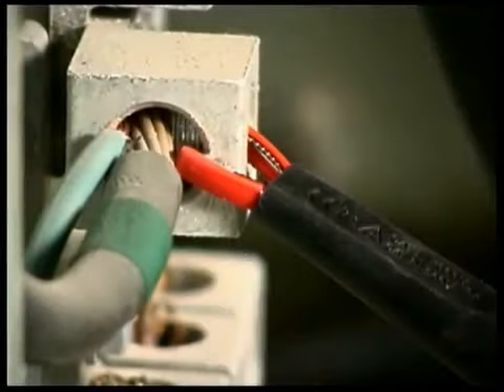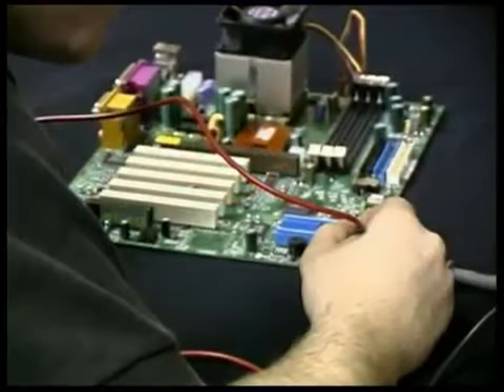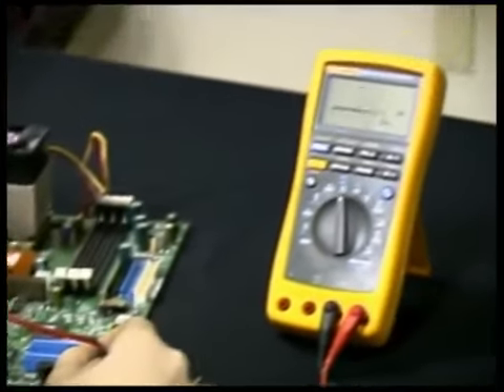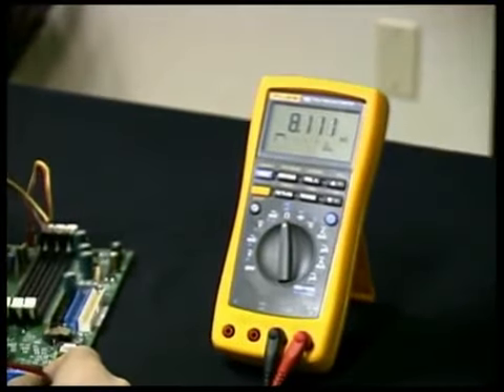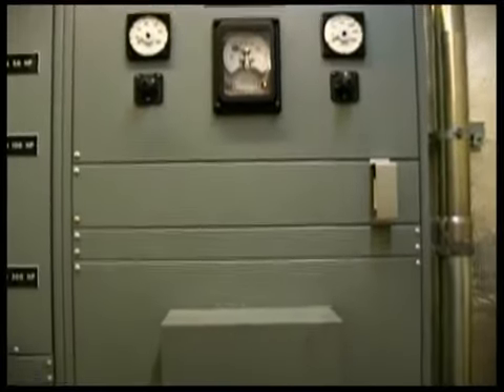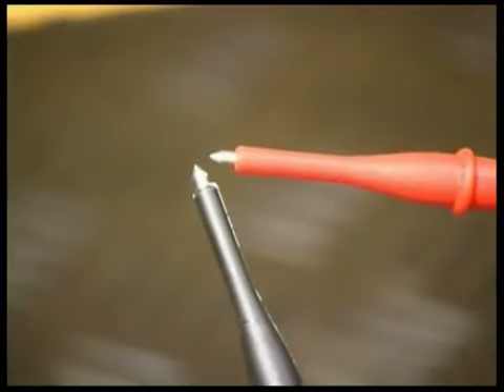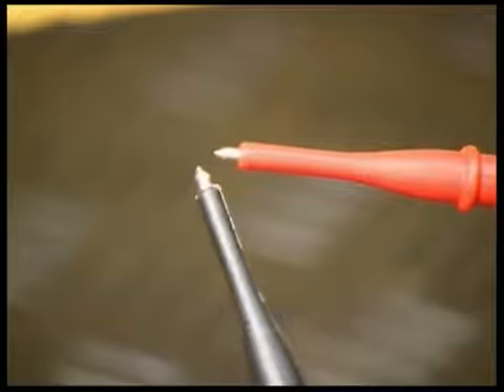Remember, test probes are designed for a variety of test environments. What is appropriate for a Cat 1 environment may not be appropriate for a 400 or 690 volt circuit. In a high-energy setting, make sure your test probes have little exposed metal. This will help avoid creating a short if your hand slips off the probes.